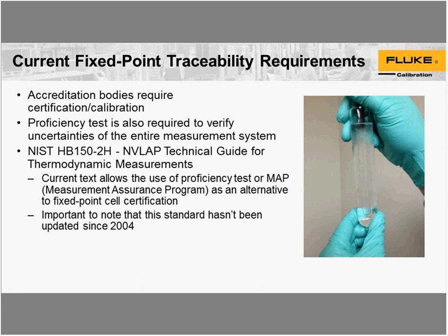In addition to that, there's also a requirement of performing a proficiency test on a fixed point system. And it's important to note the difference there. A fixed point cell being certified establishes traceability of the fixed point cell, but the proficiency test ensures that the entire system is working correctly, including the measurement technique, apparatus, and calculations, to ensure the laboratory agrees with another established laboratory.